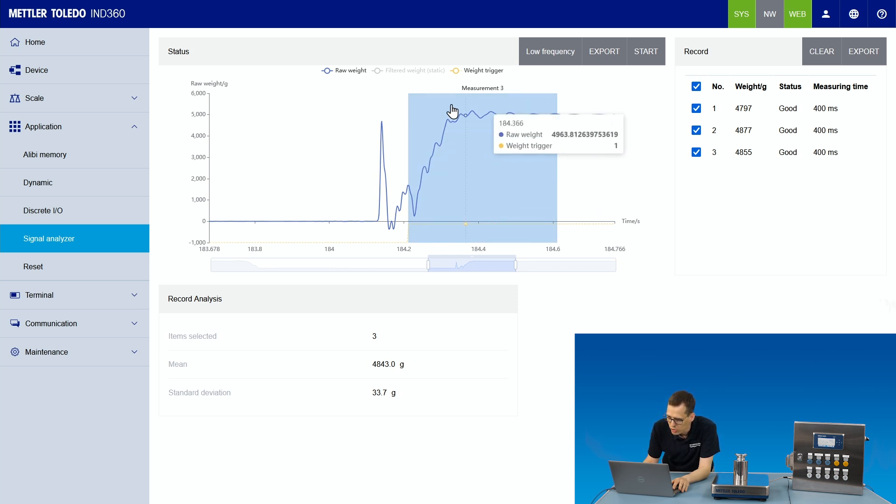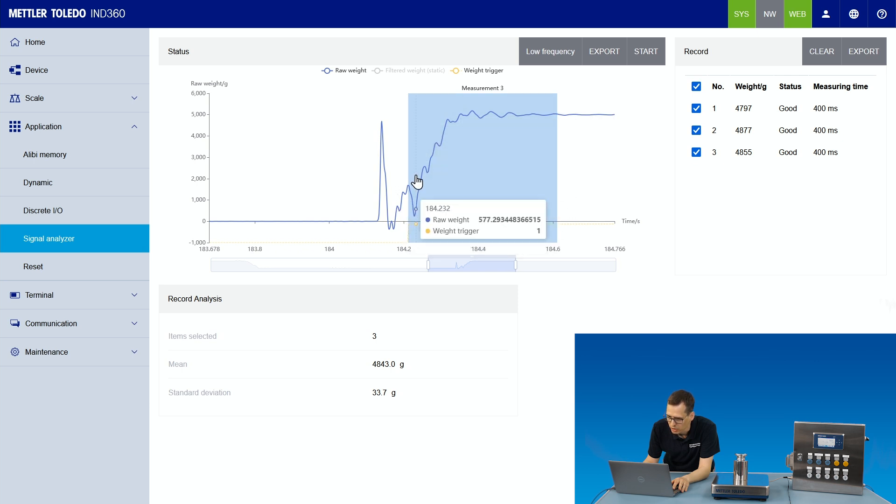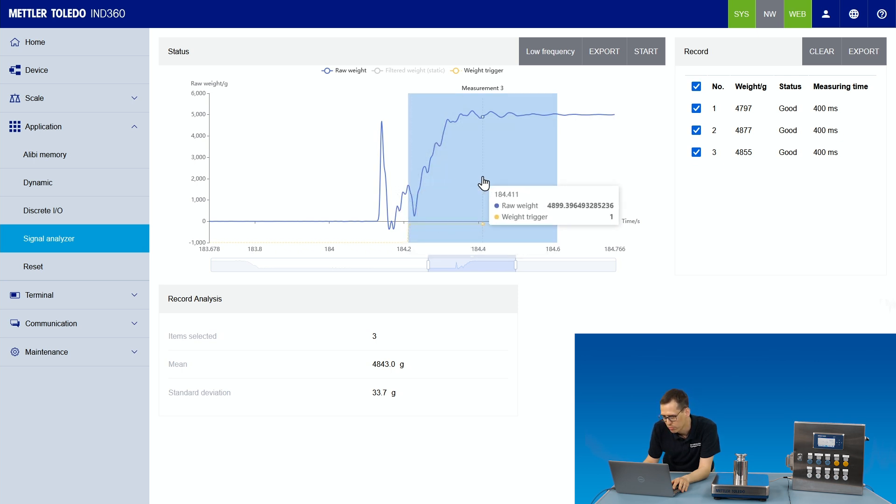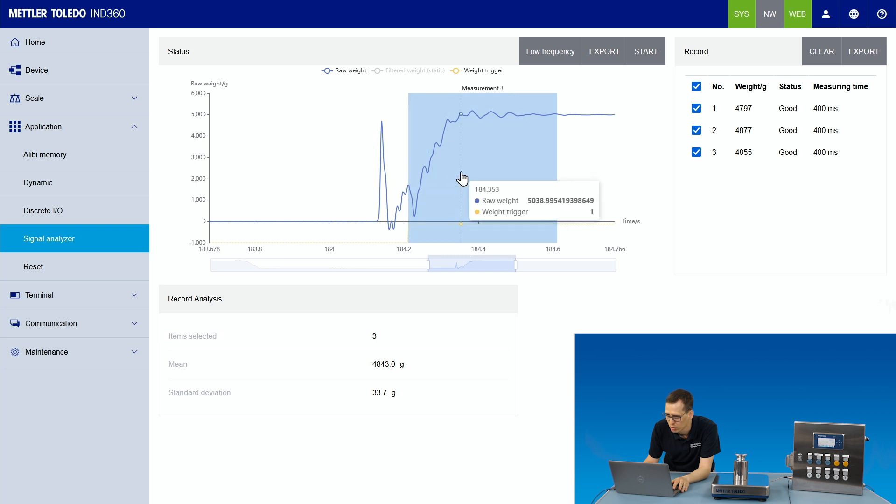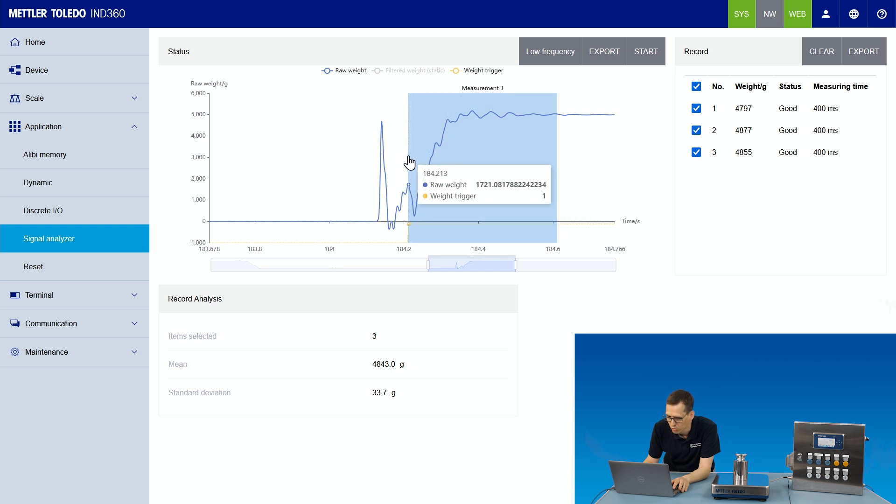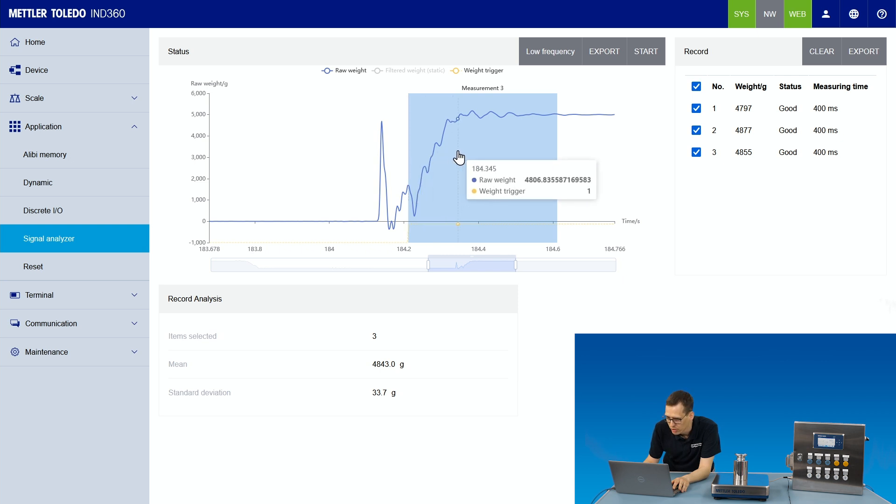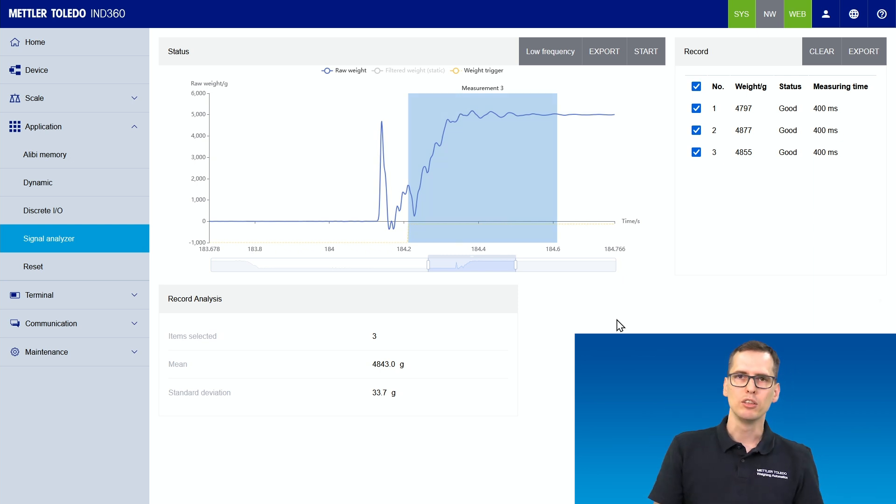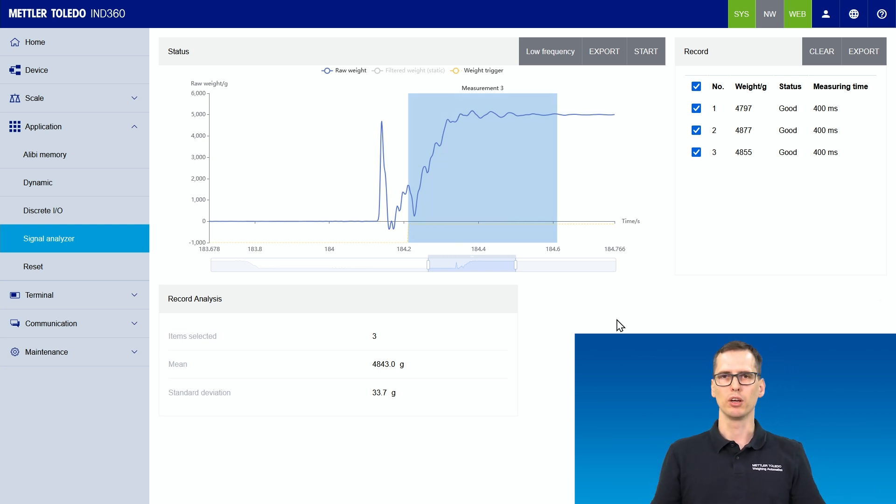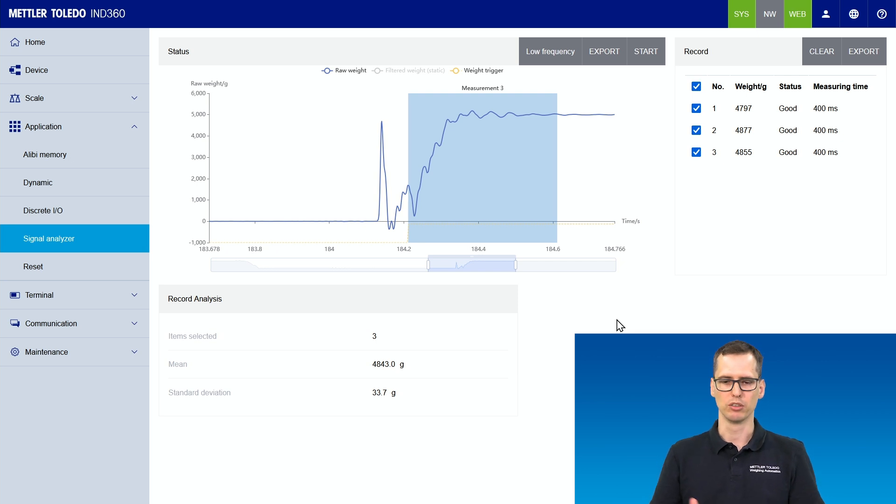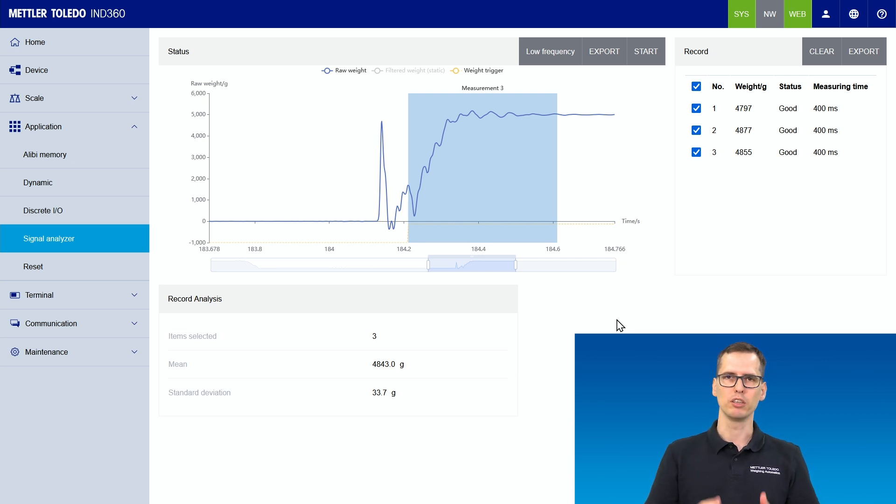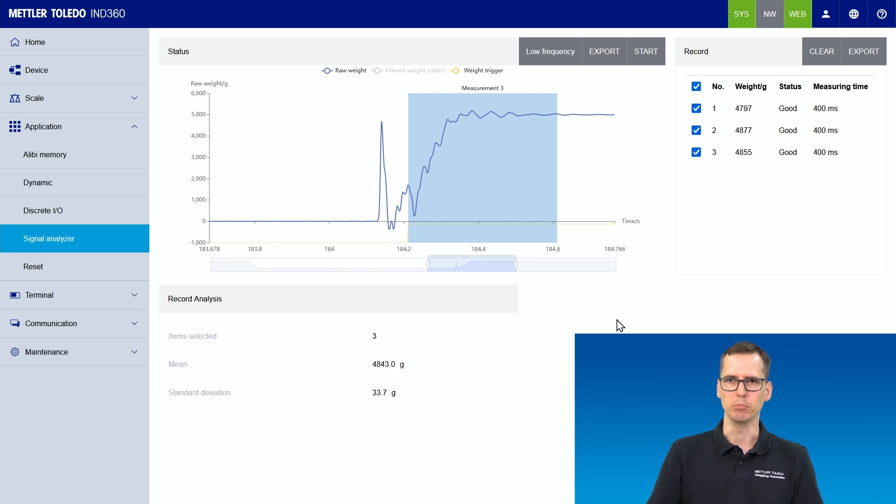This is because the measurement we take starts too early. So we need to shift this measurement window a little bit to the right. Hovering with the mouse over this timeline, I see here I have 184.213 and here 184.345. That means we need to shift the weight window about 150 milliseconds to the right to capture the weight at the right point in time.